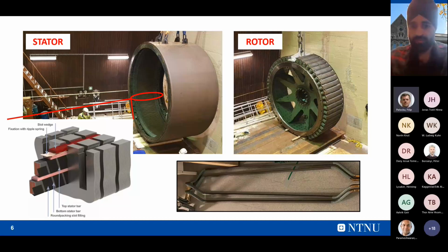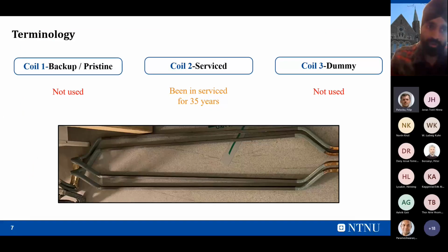So now, in the next slide, these are the terminologies I'm going to use in this presentation. This one is coil 1, which is called the backup coil or pristine coil. Coil 2 is the serviced coil, and coil 3 is the dummy coil. So basically I'm going to use three different coils. All these coils were manufactured at the same time in 1976. But coil 2, the service coil, was in service for 35 years, and after those 35 years we have taken it out.